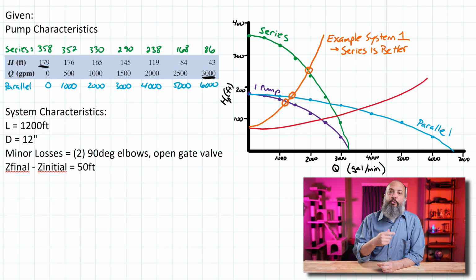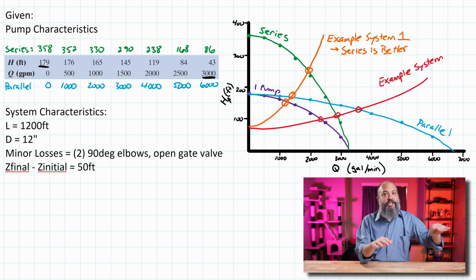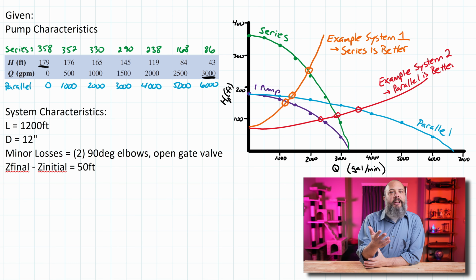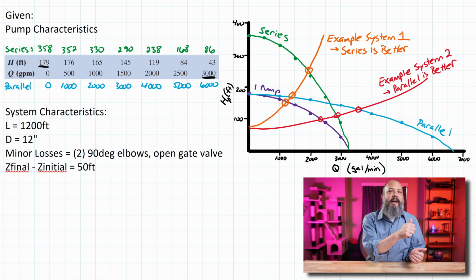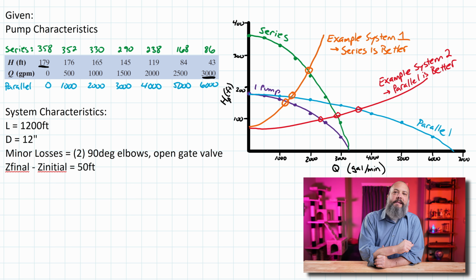Oppositely, if we look at the red example system 2 line, you'll see that for a flat, a relatively shallow system curve, parallel is going to be better. Right? In this case, the light blue intersects the red line further to the right and higher, so parallel pumps will give you both more flow, like a larger Q, larger flow rate, and higher pump head than either series or one pump.